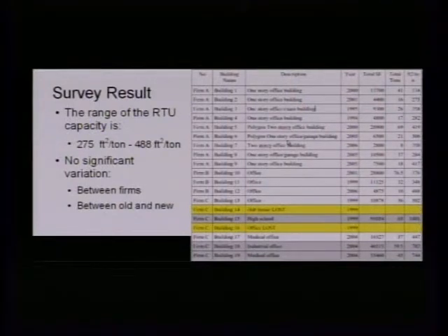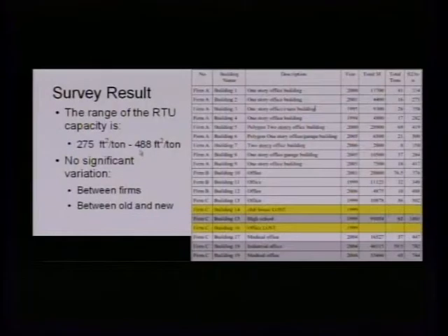So here is the summary of the results. As you can see, we list the firm, the building, a summary description, and then the year, and total square foot, and we summarize the square foot per ton. On average, it's anywhere between 275 to 488 square foot per ton of capacity. And for those of you who are not engineers, the rule of thumb for right sizing is anywhere between 400 to 600 square foot per ton. So the result of the survey is anywhere between right sized to slightly oversized.